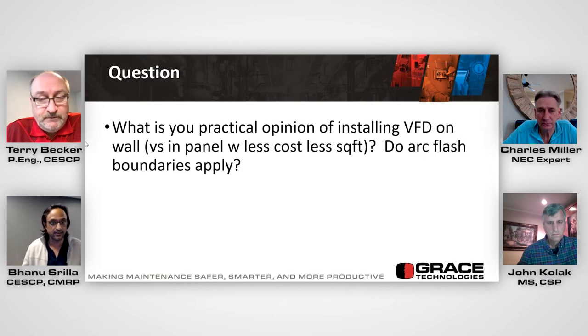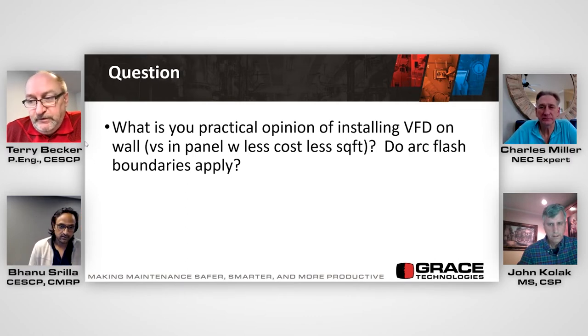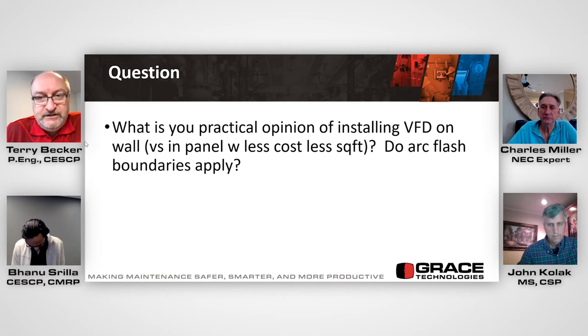They don't know what's going on here, but they are exposed to that on a regular basis. Will that create additional risk? No. VFDs are installed in process areas as well, right? So our electrical equipment is distributed in process areas where we have operation staff. They don't need arc flash PPE to be around the electrical equipment, MCC, switchgear, wall-mounted drives, drives that are part of a package. They walk up to it.